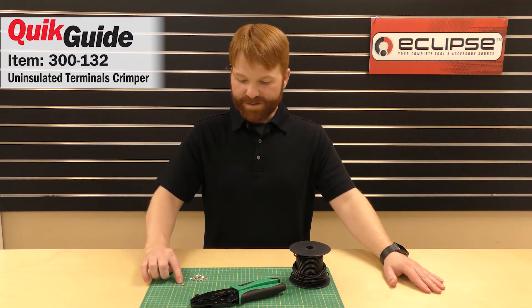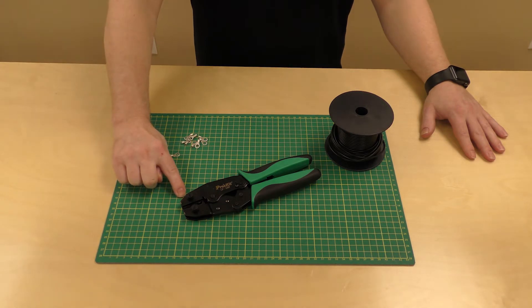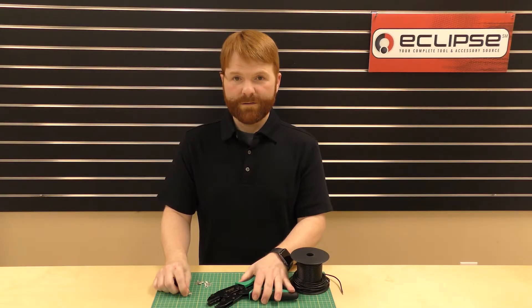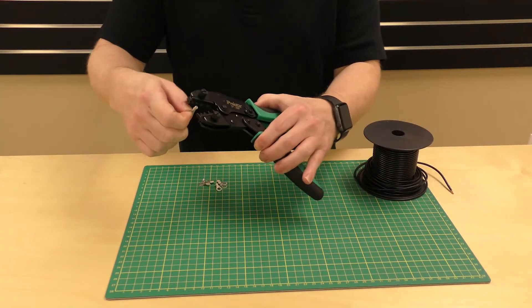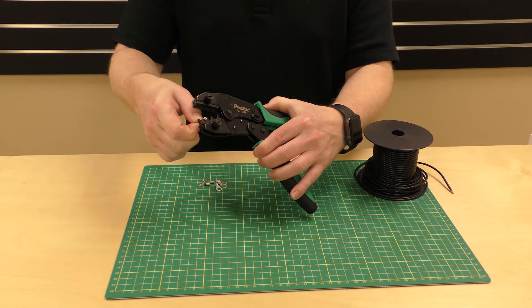In this video we'll be crimping uninsulated terminals using the 300-132 Lunar Series Crimper. Our first step is to put the terminal into the die set. Now squeeze the handles just enough to hold the terminal in place.